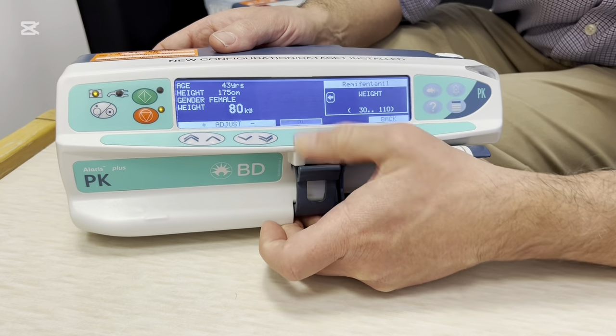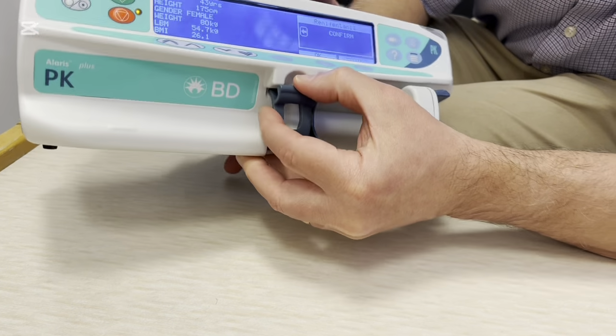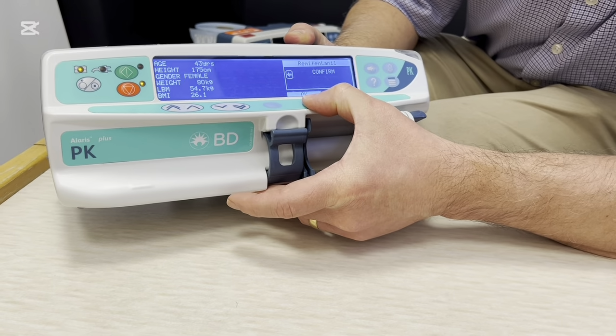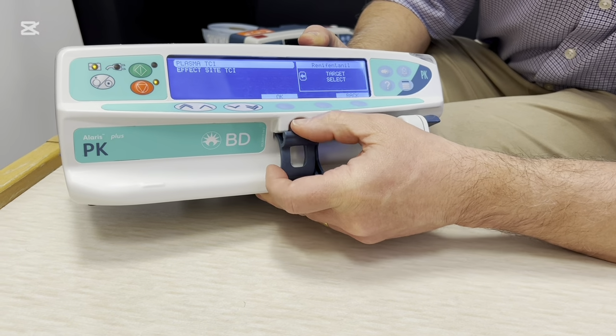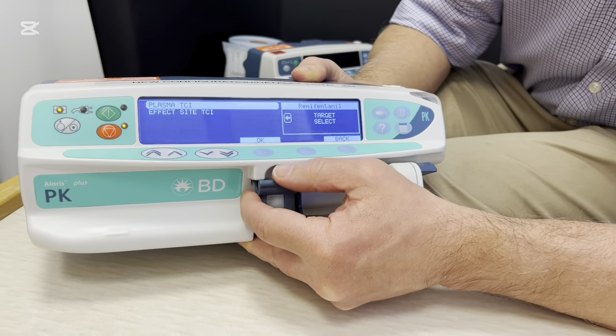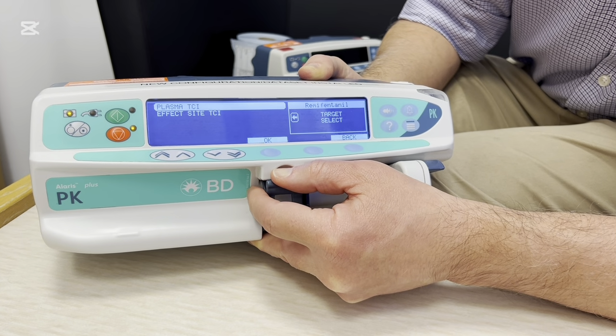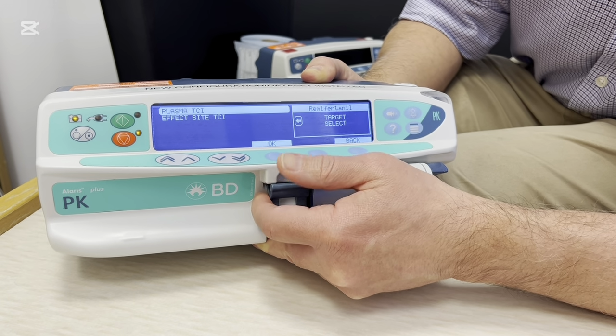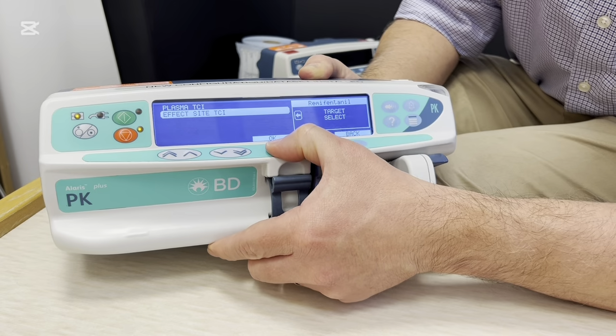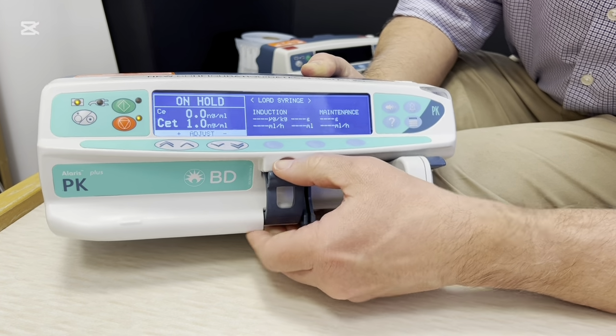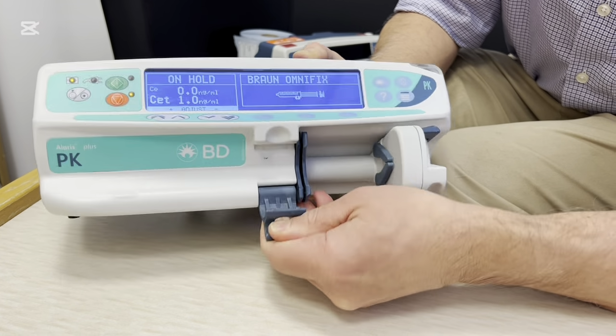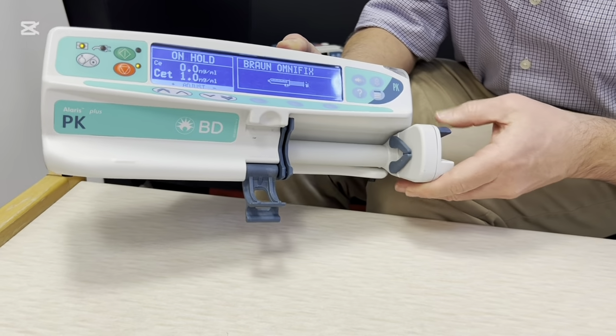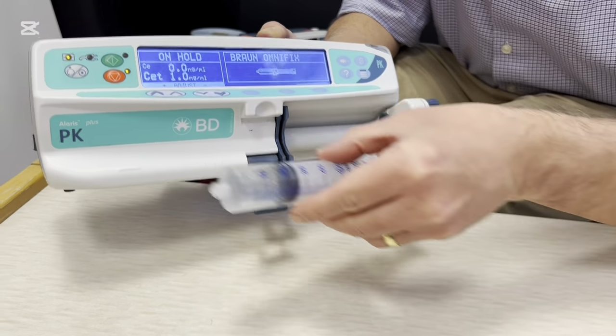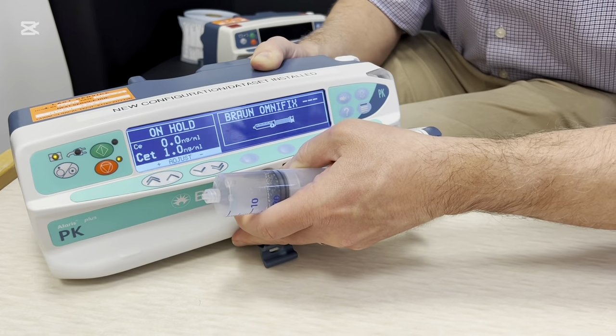So we'll press OK. And then it asks us to confirm the recipe that we've got. And the other options are to confirm whether you want to go for plasma target controlled infusion or effect site target controlled infusion. So we'll go for an effect site and press OK. So we now need to load the syringe. So as with the GH, it's a matter of opening the syringe clamp, moving the slide along, and then placing the syringe.